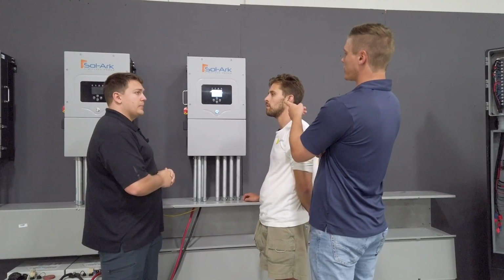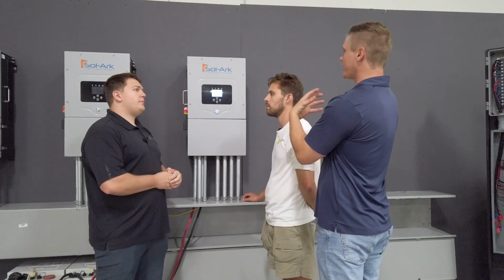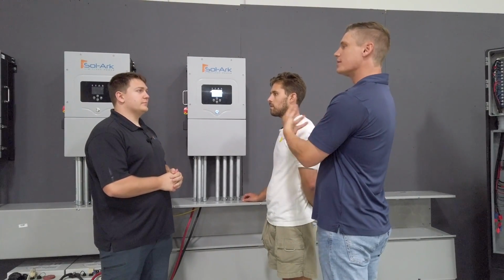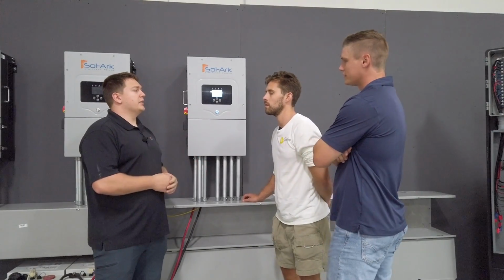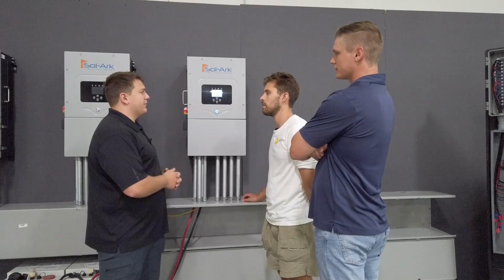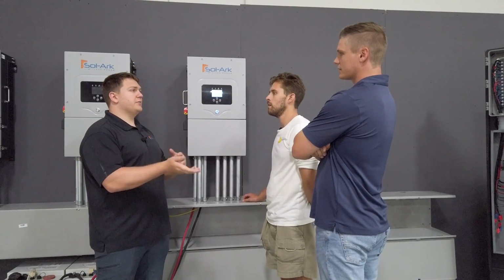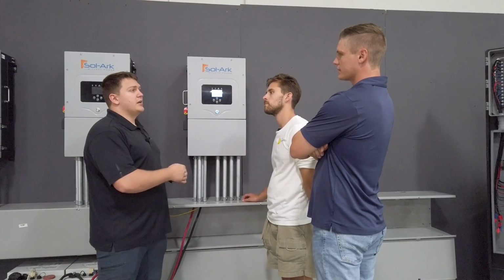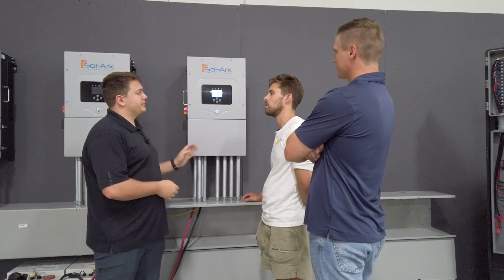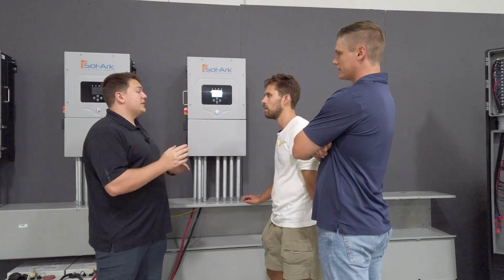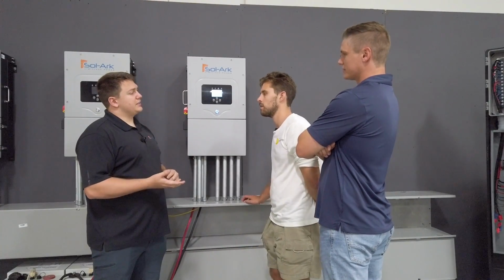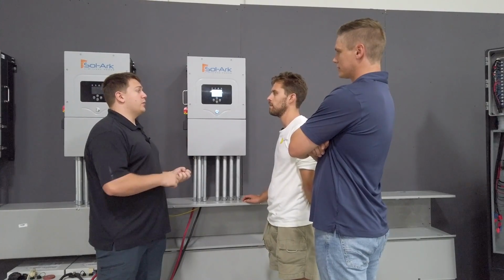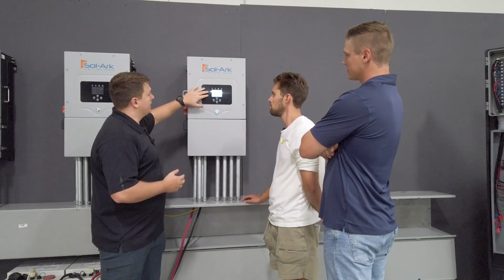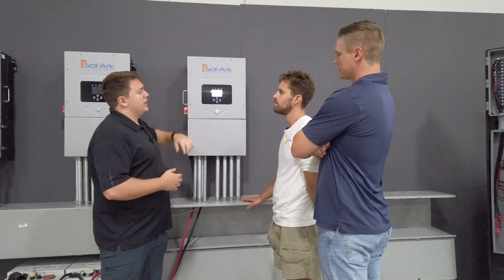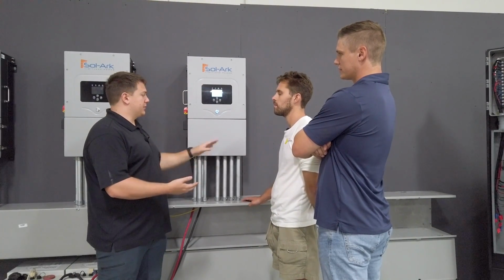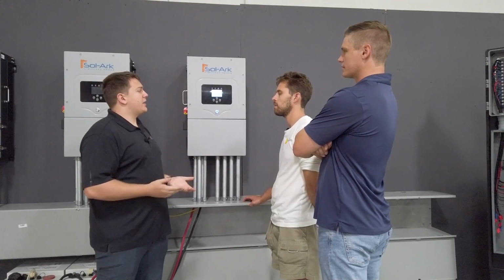Okay. So this is where we're going to adjust if we've got a generator, or something like a different PV system in there. Correct? Yeah, so if you're doing a retrofit and the customer already has 7 kW of PV up on the roof with microinverters or something like that, you can just pipe that right into the generator input and the Sol-Ark will control it. Very cool. And you said load shedding as well? Yes, so it's either or, not both at the same time, but if you didn't have to AC couple, you could use it as a smart load output, and that's going to let you pick some settings on here so that if your battery gets below this set point, we will cease powering the load or the gen breaker, so you have automatic load shedding.